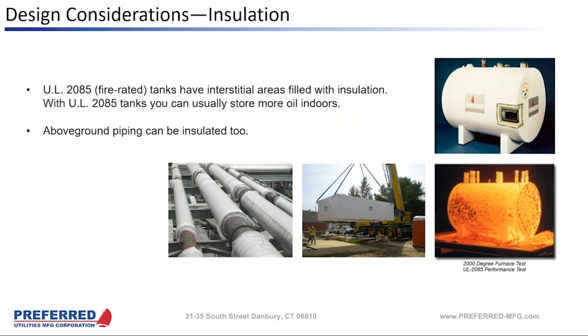Okay, so another thing you can do, and Alex touched on this, is specify UL 2085 fire rated tanks. Fire rated tanks have their interstitial filled with insulation, and that insulation will help keep your tank warm in cold weather. And then it's a good idea to insulate above ground piping as well in cold places, just to cut down on the heat transfer in cold ambience.